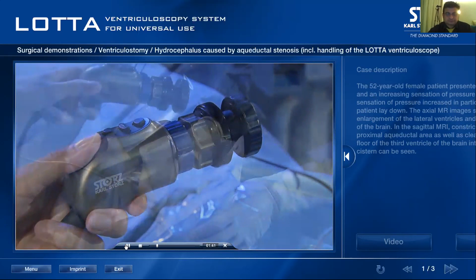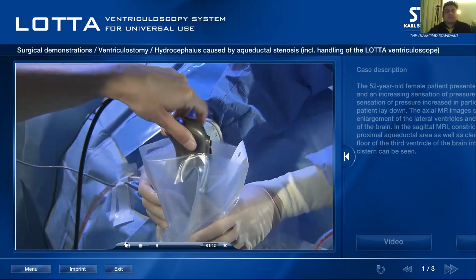Which allows the telescopes to be changed under sterile conditions during the operation. Because the inner portion of the camera head is unsterile. If we do not use the adapter and then change the endoscope, it is not going to follow an aseptic technique when you change the scopes between a 0 degree, 30 degree and 45 degree, or from diagnostic to therapeutic scope. The sterile cover is then pulled over the camera to avoid having to sterilize the camera, which reduces its service life.